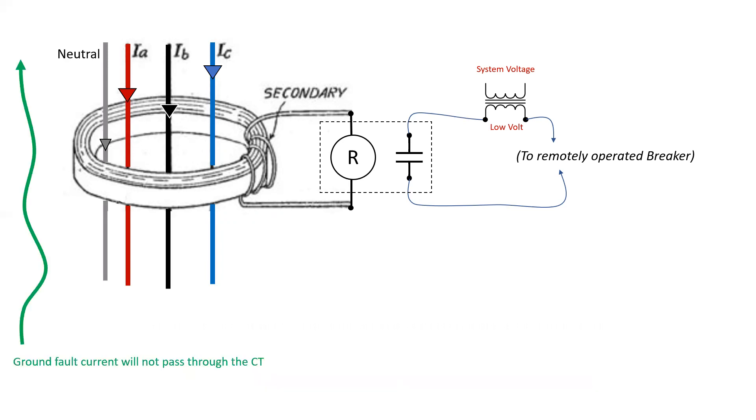So here we have some ground fault current that is not passing through the CT, which causes a resultant flux. This will cause current to flow in the secondary of the CT, which causes a voltage to be developed across the coil of the relay. The relay energizes, closing the contacts and applying voltage to the shunt trip breaker, which opens the breaker.